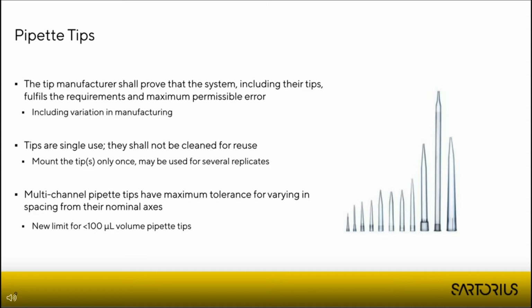And then for multi-channel pipettes specifically, there is a new limit for under 100 microliter volume pipette tips, how much they can vary in the nominal space. And in more practical terms, this means how bent the tips can be. There were already limits in the first revision for other types of tips, but now, especially for the smaller volume, there are more strict rules in place. And I do believe the reasoning is clear because we are moving more towards smaller micro-well plates. So the tips, especially the small tips, need to be very straight, so you don't face any problems when hitting the wells.